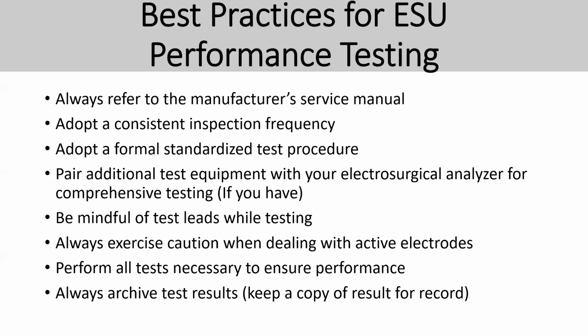Be mindful of the test lead while testing. Check the cables, arrange them nicely, and test properly. Always exercise caution when dealing with the active electrode. Remember, electrosurgical units are quite dangerous, so make sure you do it properly. Safety first, because it can really cut someone during the work. So be careful. If you're wearing a ring, wedding ring or whatever, please remove it from your finger, because sometimes when you touch it, it can cut your finger. Just be careful.